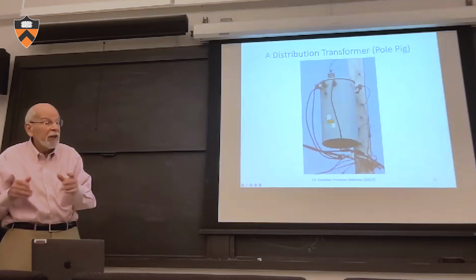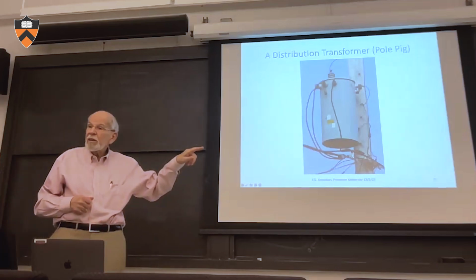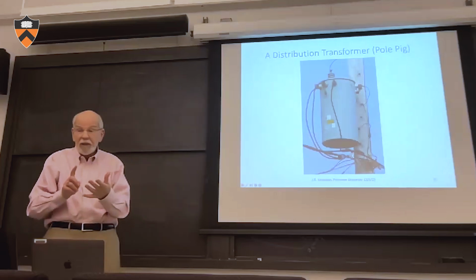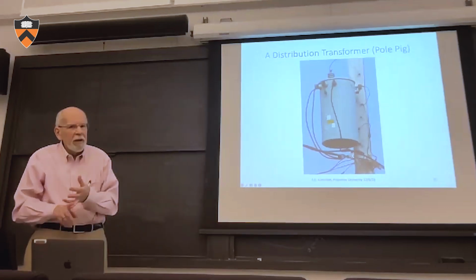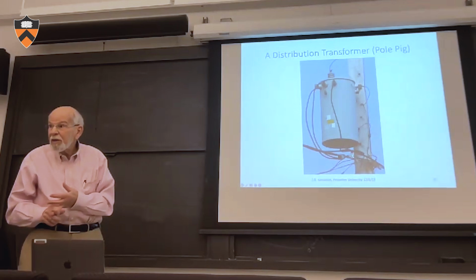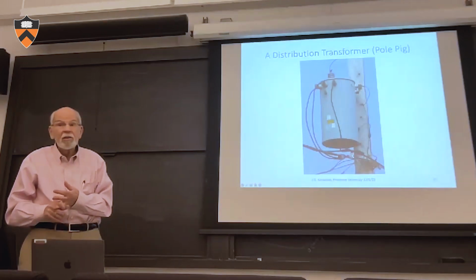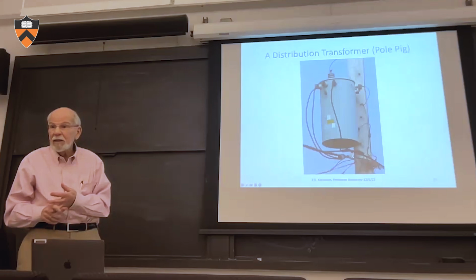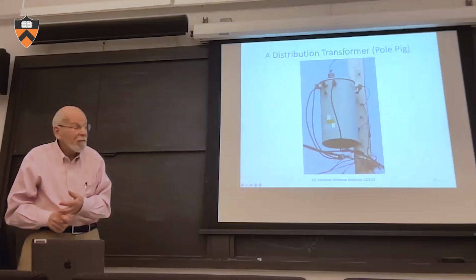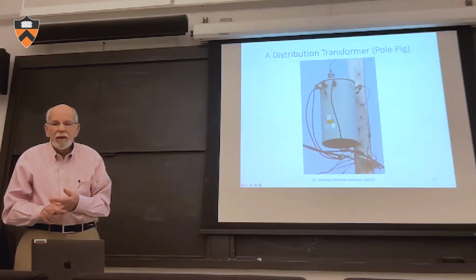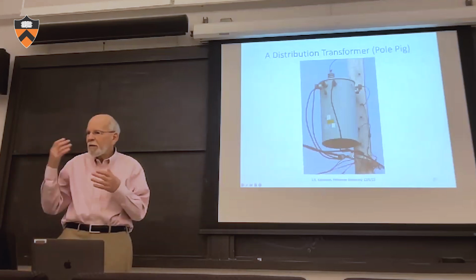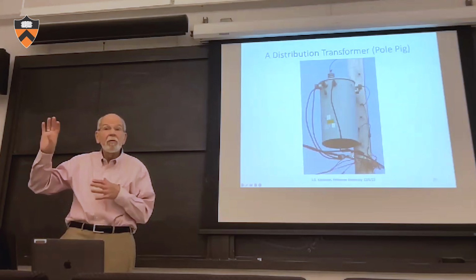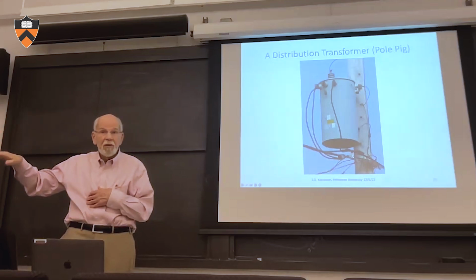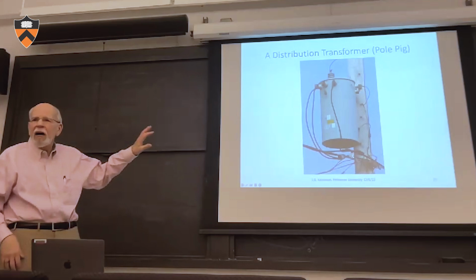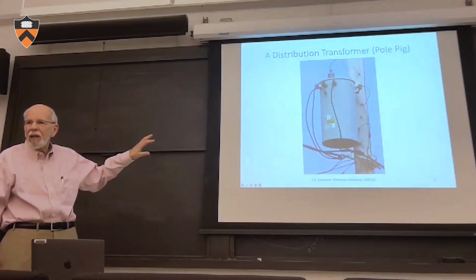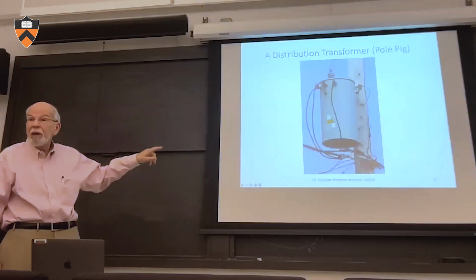With a solid state transformer, if you could replace that, then you had control. When the load was low, you had no core loss because the voltage is no longer high on a big transformer. You had the ability to monitor what the power flow was so that you could tell whether there was a problem at a particular location. So you can imagine the kind of versatility that a solid state transformer would bring to the party in this particular application.